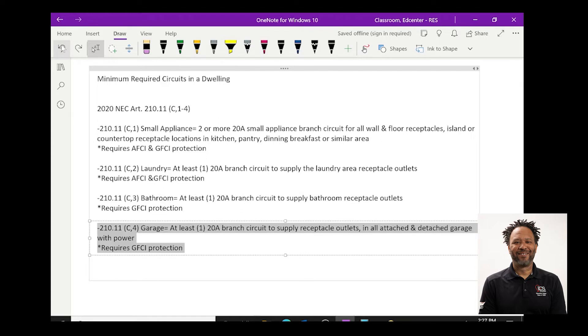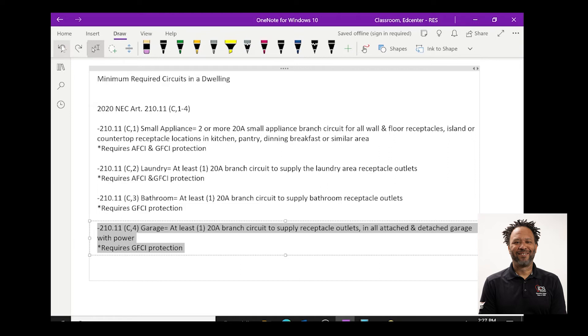The last required circuit for a home is your garage and that is found in article 210.11c4 and this states that at least one 20 amp branch circuit to supply receptacle outlets in all attached and detached garages with power.